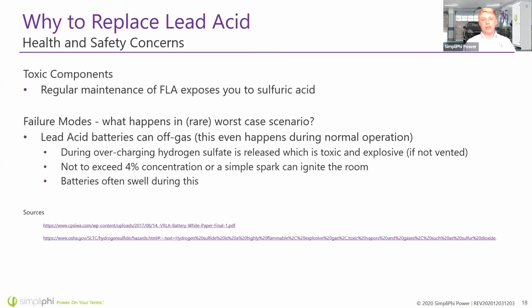If you're not changing your system layout, don't have additional needs, and your capacity isn't reduced, your batteries are working fine—so why would you ever pull out your lead acid batteries? Well, maybe you're concerned about your health and safety, and that's a valid concern, because regular maintenance of flooded lead acid batteries exposes you to sulfuric acid, which is not good. We'll talk more about this later in the webinar, but ultimately you definitely don't want to do maintenance on flooded lead acid batteries without proper protection. I see a lot of people being really nonchalant about this, just flinging around a hydrometer with sulfuric acid on it while wearing a t-shirt and no glasses, not realizing the damage that can have on their skin and eyes.